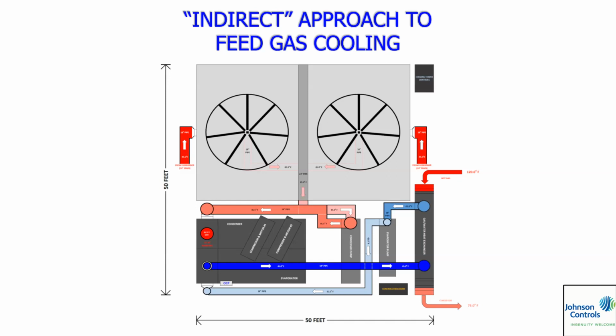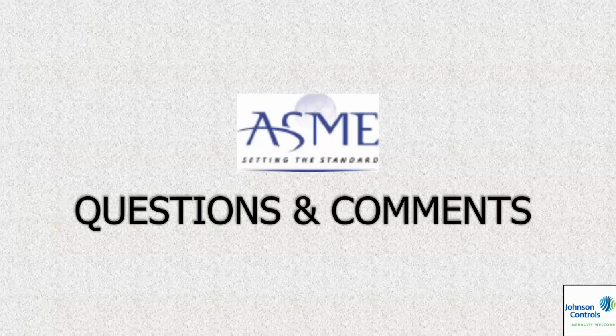The water used in these systems is all specially treated, right? On the cooling, if you're using cooling towers, yeah, you definitely want water treatment services. Normally there's chemical treatment companies, even for the water used. On the evaporator side, yeah, they normally treat that water, but it's a closed loop system, right? Yeah, they'll initially treat it and then they close it up.